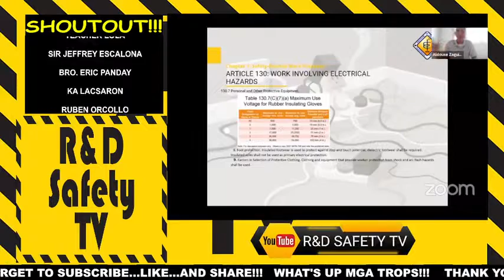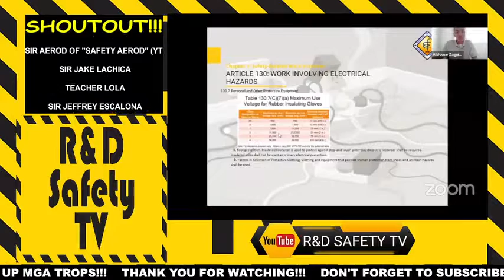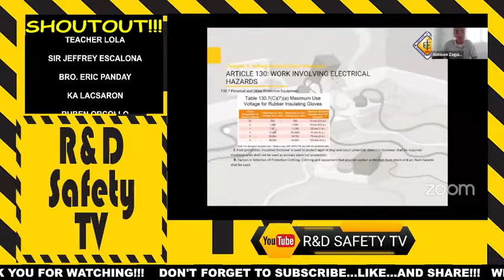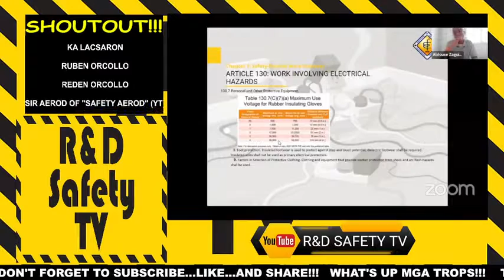So maximum AC use - say distribution inside the building or factory, minsan mga 4160, so you'll use class 1. Pagka sa entrada, yung first private pole niyo, maybe kung outside Metro Manila, that's probably 13.8 kV, so class 2. If you're in Manila, 34.5, so class 4 ang gagamitin niyo diyan. If you're doing that work from the first private pole to your main switchgear, that's probably the rubber gloves na kakailangan niyo.